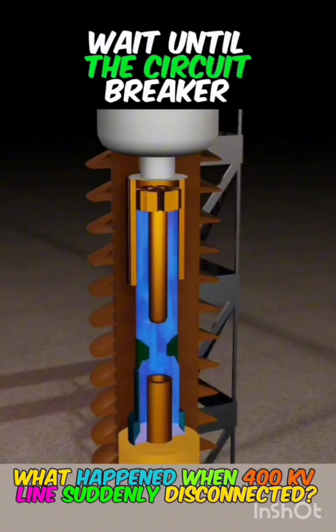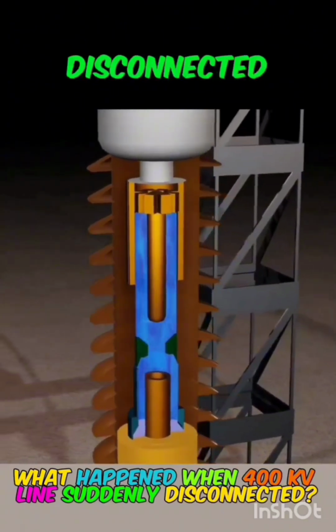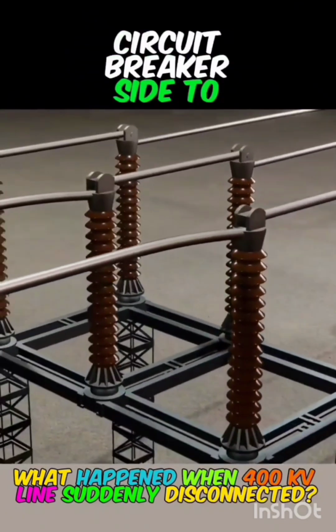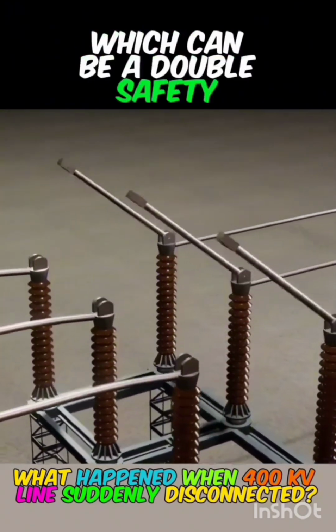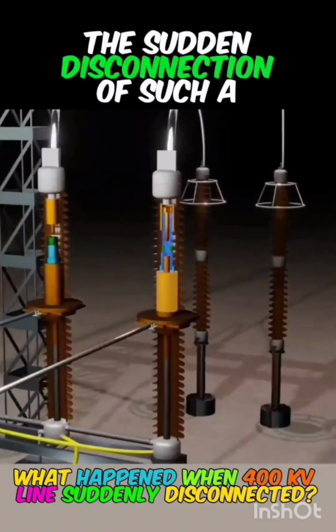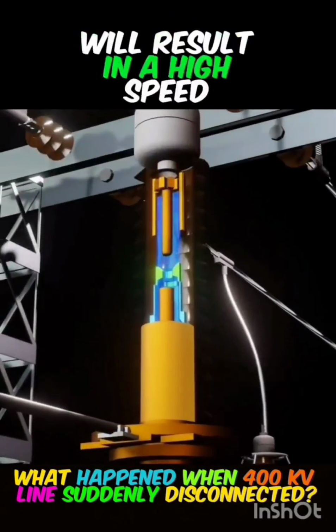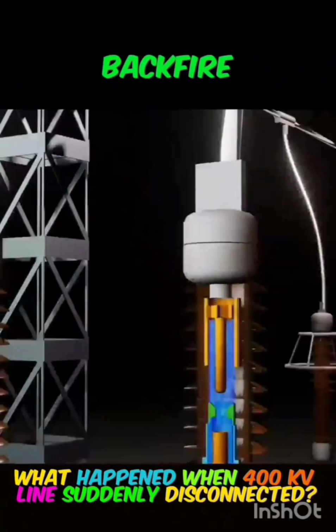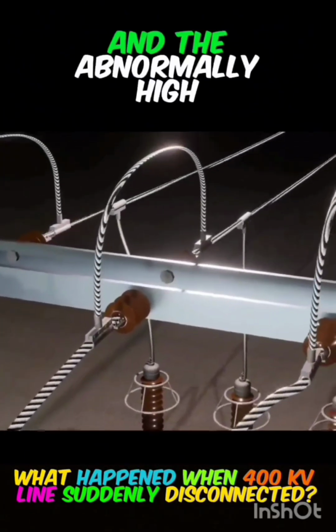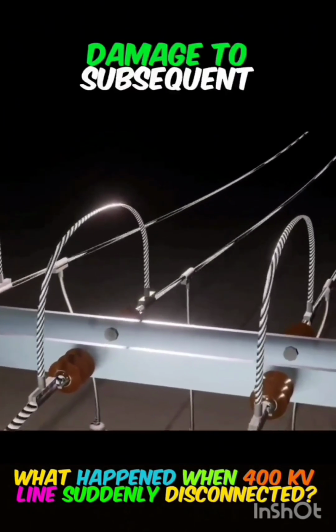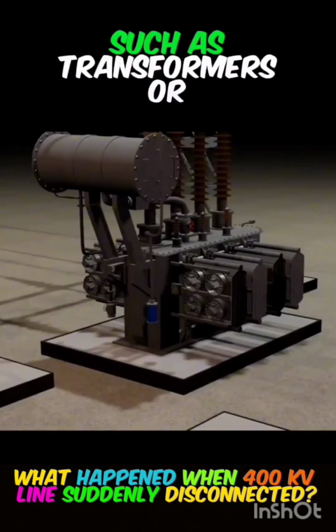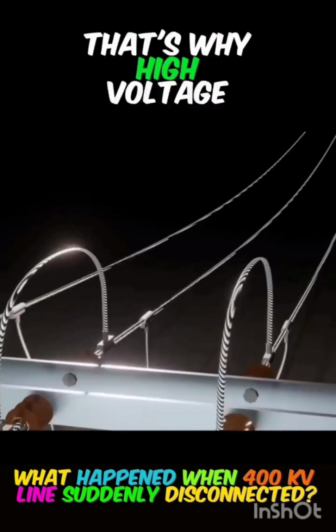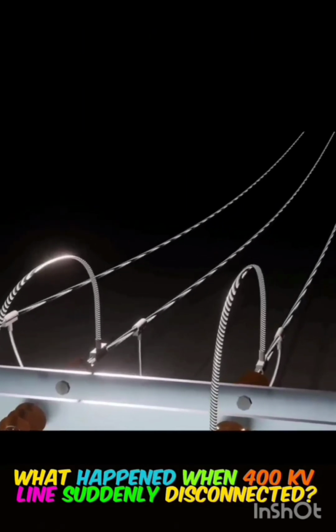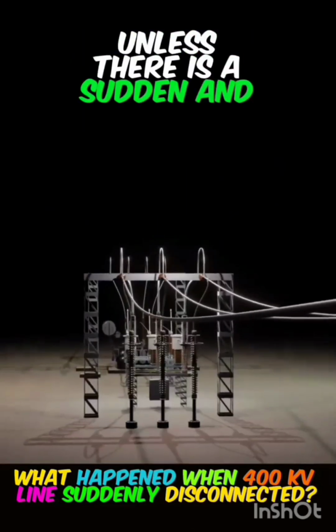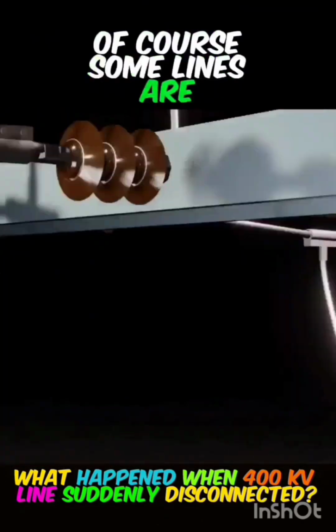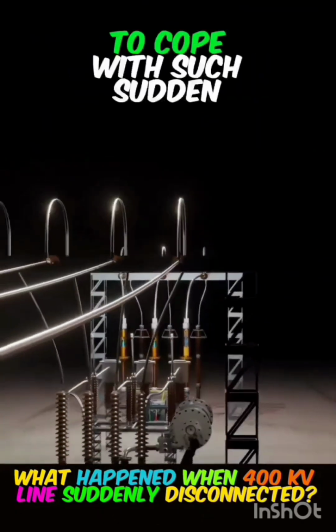Wait until the circuit breaker side is completely disconnected, and then go back to the manual side to open the isolator, which is a double safety guarantee. The sudden disconnection of such a powerful line will result in a high-speed flow of current that will backfire from the circuit breaker's contacts, and the abnormally high current may cause damage to subsequent electrical equipment, such as transformers or generators. That's why high-voltage transmission lines are not randomly disconnected, unless there is a sudden and significant situation. Of course, some lines are equipped with measures to redistribute the current load to cope with such sudden disconnections.